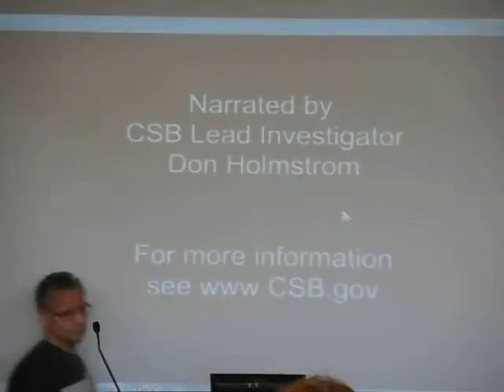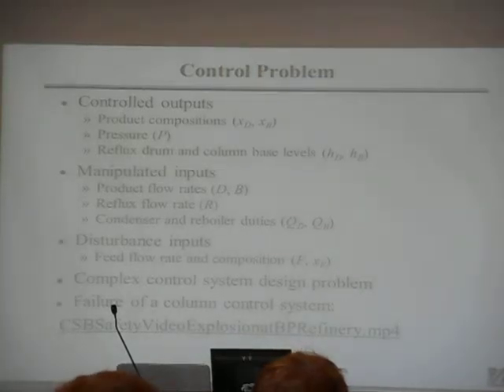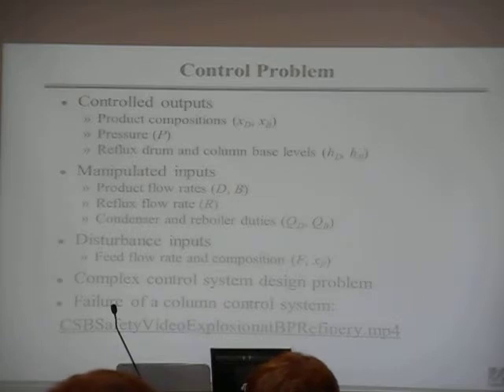That's not a pleasant video, but hopefully you get the idea. When you guys get jobs, the stakes are a lot higher than in any app or exam. If you look at what happened in this case, it's a combination of instrument failure — that thing wasn't working, that valve didn't work, that indicator was saying it was dropping when it was at 130 feet — and also operator error, when someone didn't open the flow out of the column as required.